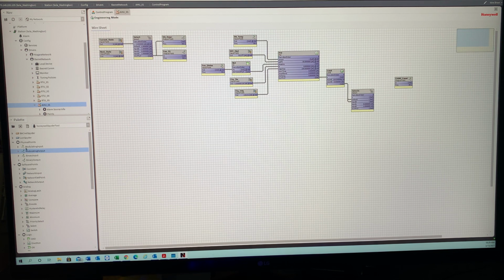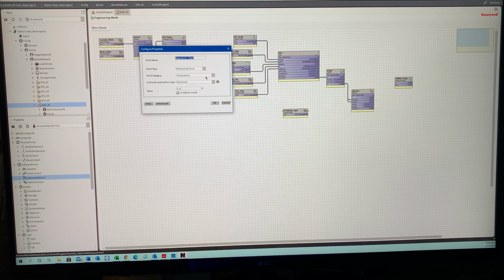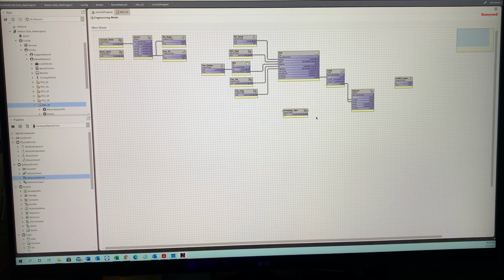So what we can do is a network set point. I'm going to call this humidity set point. All right, so we're going to go configure. I'll bring this over here. Do a percentage. And we're going to say anything above 60%. The good part is we're making it adjustable. So if they want something tighter, 50, 55, for comfort's sake, that's where the humidity set point comes in really great.